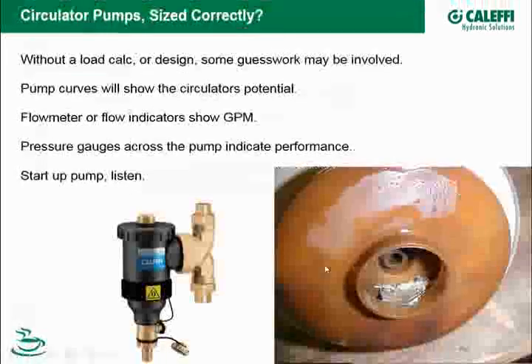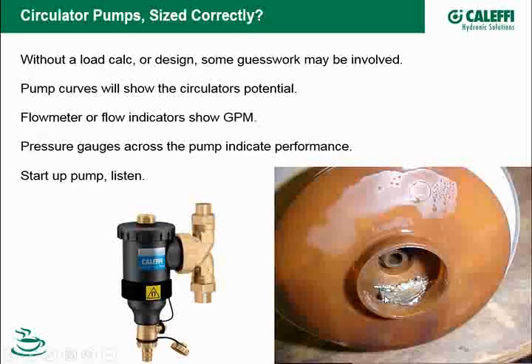Again, another case of a pump that came out of a system. You can see some of the solder there. When they soldered some of the joints in there, they had some of the solder laying inside the fitting, and of course it worked its way through the system. It got inside the impeller here, which obviously is going to change the performance of that pump. And in some cases, if you get a glob of solder or some kind of dirt on one side of the impeller like that, it's going to throw them out of balance, and they'll shake and they'll vibrate, and they're not going to last very long.